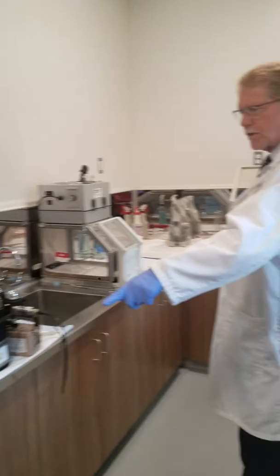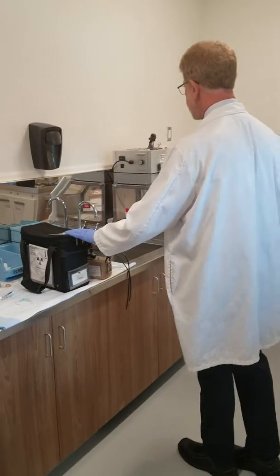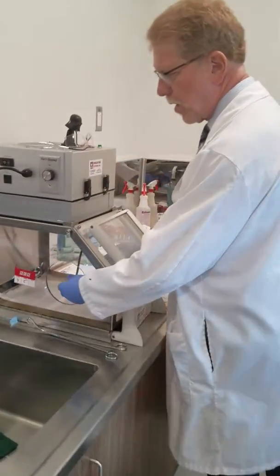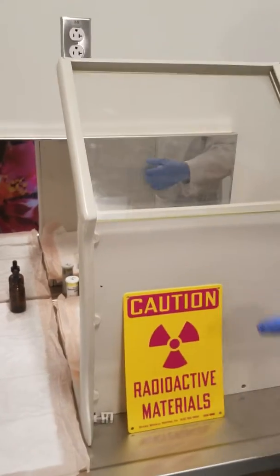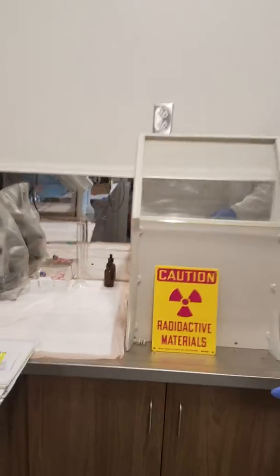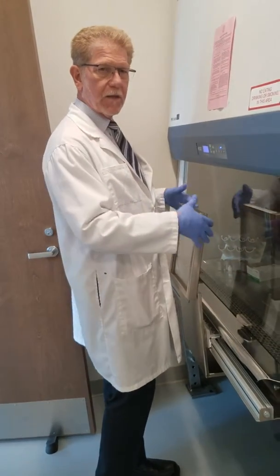The rest of the hot lab: we have a storage area for our radioactive sources that actually go on the gamma camera. We have a dose here that's arrived from the radio pharmacy. We have a mini L-block with a small clean air environment, and then we have a large L-block that's not inside the clean air environment. In these two L-blocks we have lead glass and solid lead where we can actually work with our radiopharmaceuticals. We can either compound or prepare patient doses.